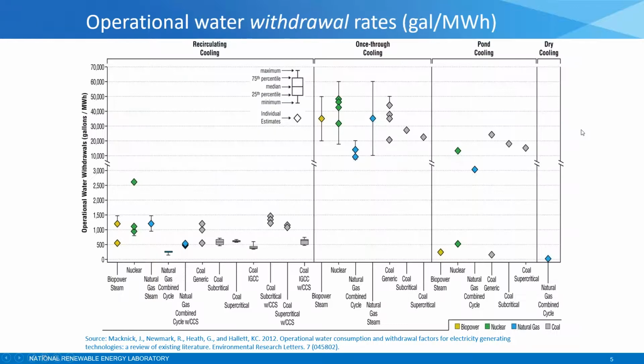If we go to the next slide, I'll show some quantitative descriptions from work we've done looking at how much water different technologies use. This figure shows a lot, but let's focus on the major trends. The middle column is for once-through cooling technologies, where water requirements range anywhere from 10,000 gallons up to 50,000 gallons per megawatt hour of electricity generated. This is a few orders of magnitude more than the water withdrawn for recirculating cooling technologies in the left panel, ranging from about 500 to around 1,000 gallons per megawatt hour of electricity generated. Other technologies have values in between, but it's important to highlight that we're looking at a 20 to 100 times difference in the amount of water withdrawn per unit of electricity generated.